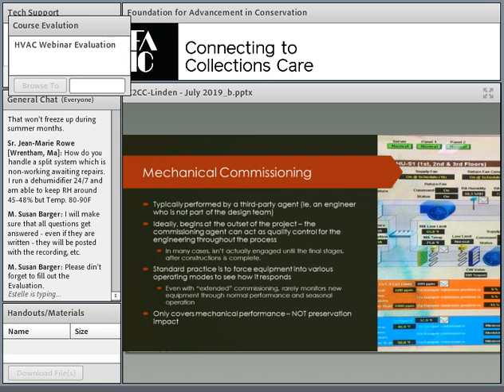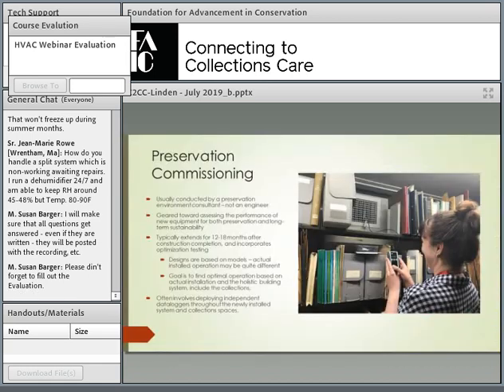It may only happen over a week or two, which doesn't tell you, if done in the middle of summer, how the system will actually operate in the dead of January or February. So keep that in mind: mechanical commissioning might force the system into different operations, but it doesn't tell you how it's going to transition between operations on a day-to-day basis.